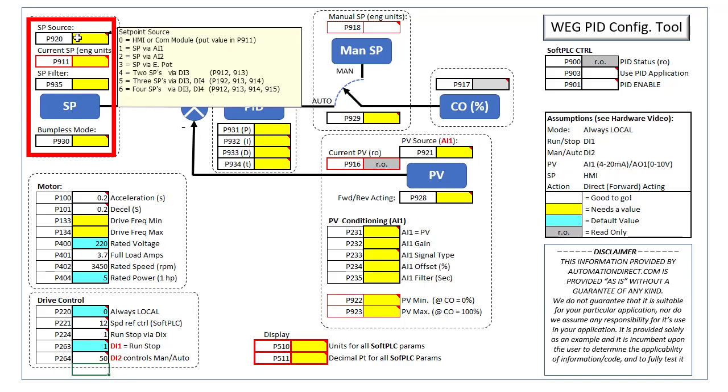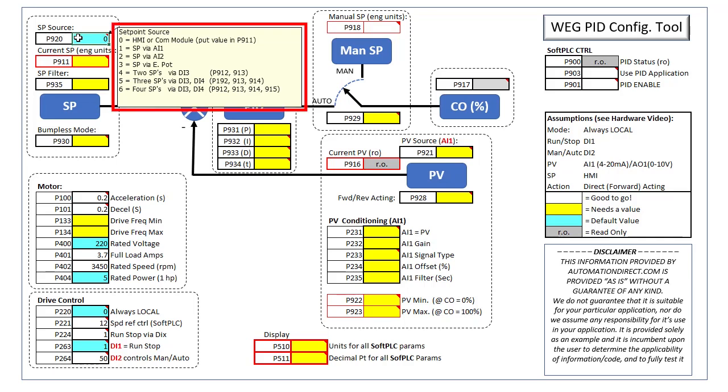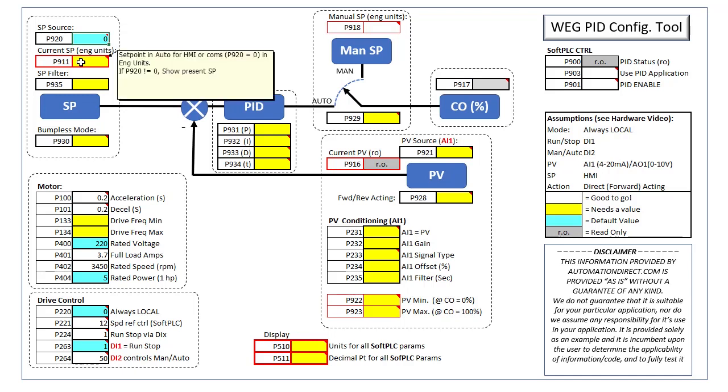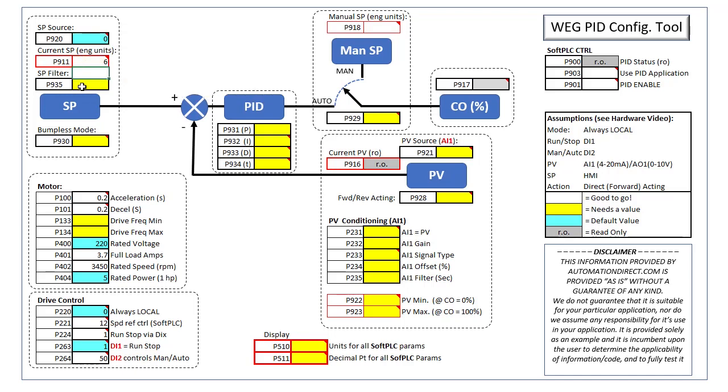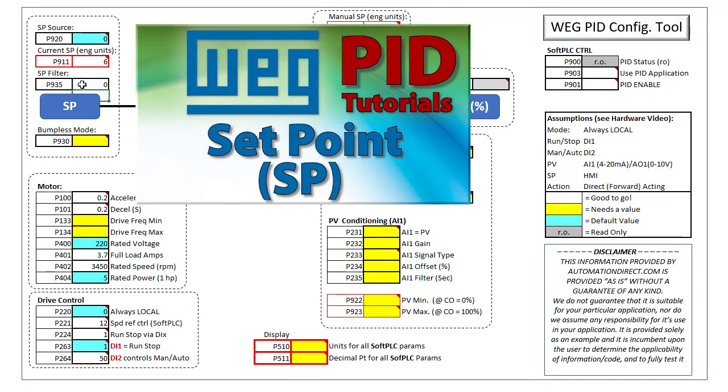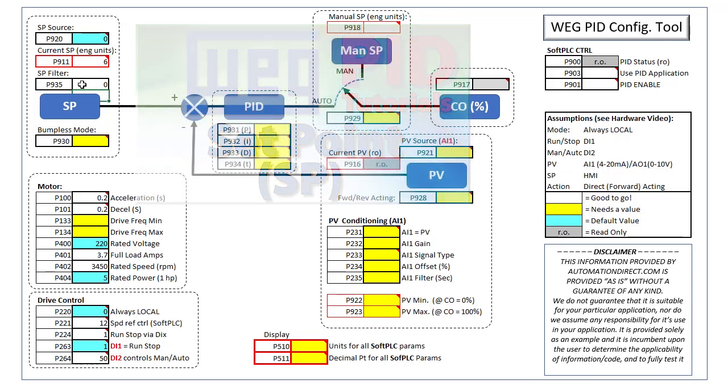Let's start with the set point parameters. We want the set point to come from the drives HMI keypad, so we put a zero here. I've added comments like this to most of the blocks to help guide you, but I'm not guaranteeing I typed everything exactly right, so please double check with the user manual if in doubt. We want our set point to be 6 PSI, so I'll put that here. We can filter the set point if we are driving it from an analog input. We aren't so we'll set it to zero. The set point video covers all of the various set point options.